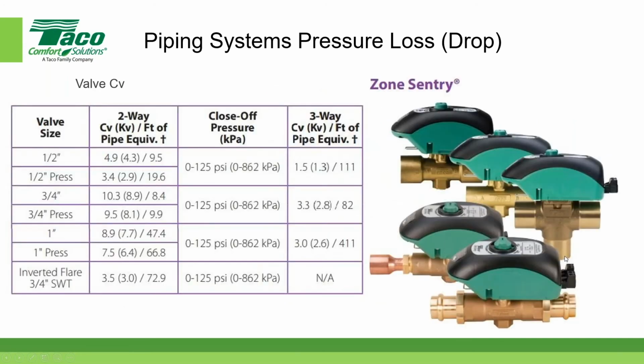Okay, here's a little table from one of our valves, our Zone Sentry valve. If you'll notice, for the different valve sizes, we give the value for the CV, the kV, and the feet of equivalent pipe length. So this first value, 4.9, let me get the little highlighter over here so you can see what I'm talking about. If I had a 1/2 inch valve, its CV would be 4.9, its kV would be 4.3, and the equivalent length of straight pipe would be 9.5 feet.